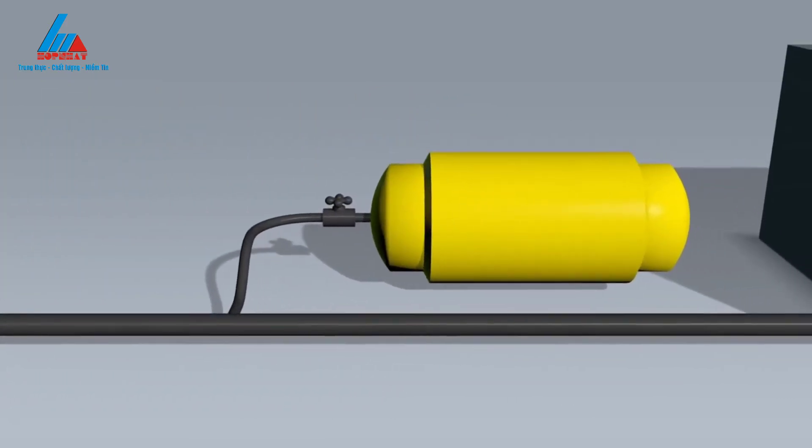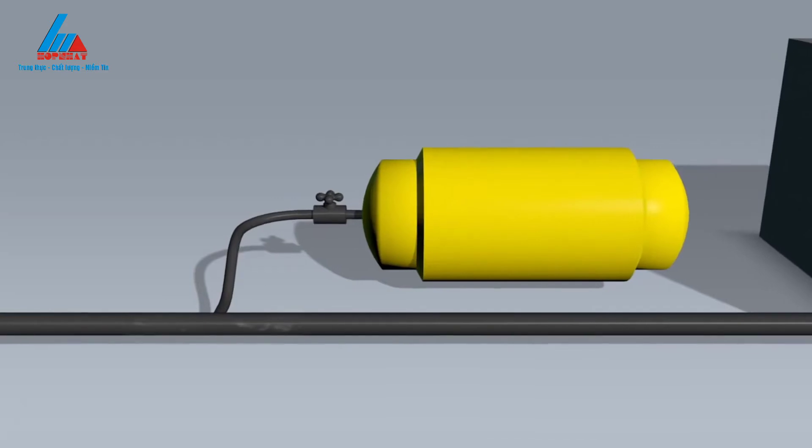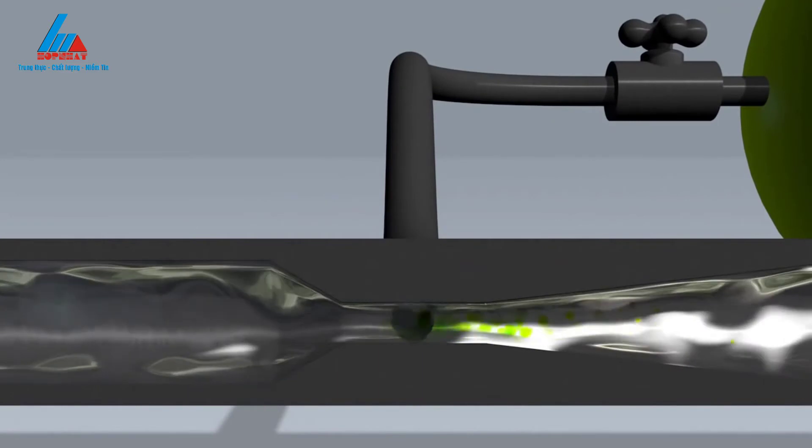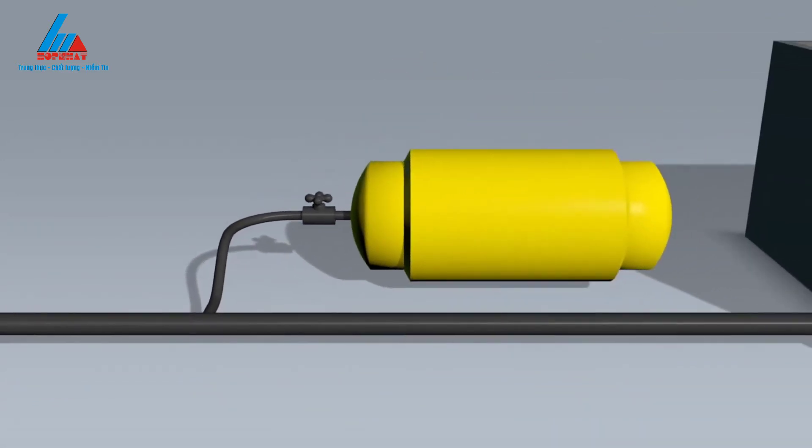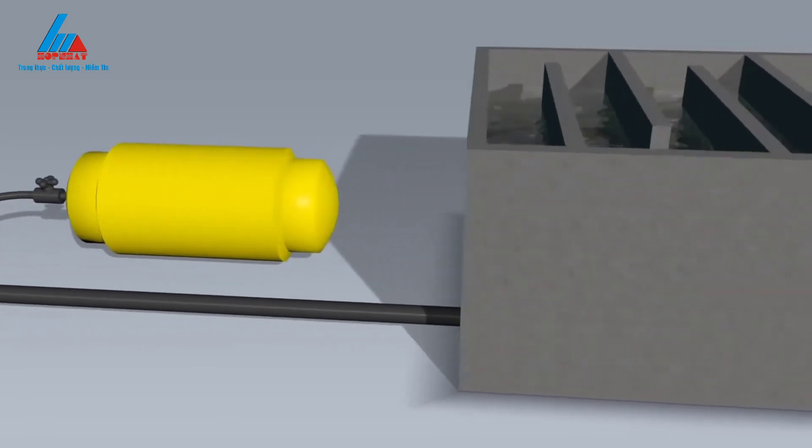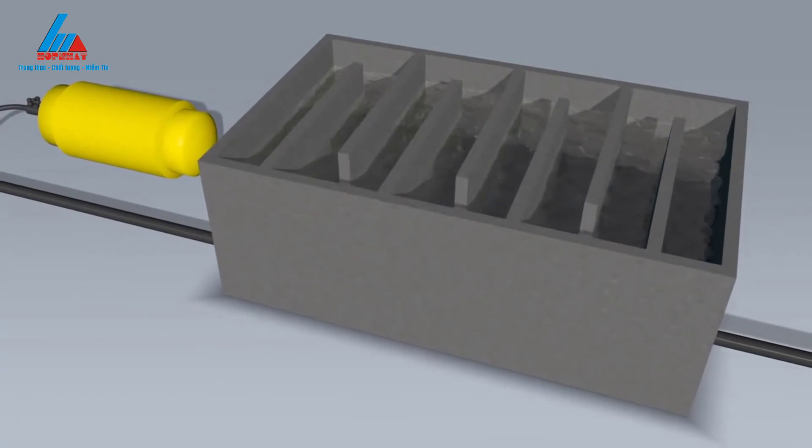The water must now go through the disinfection stage to eliminate hazardous microorganisms. Several processes can be used for this, but the most common is chlorination. Chlorine gas is dispersed into the water, forming hypochlorous acid to destroy dangerous bacteria and viruses. The chlorine is then left in contact with the water for a while to allow for thorough disinfection.